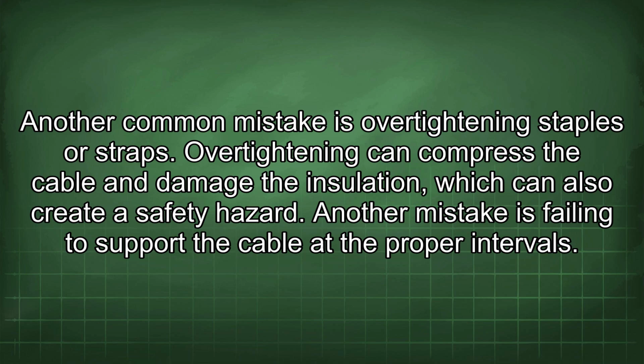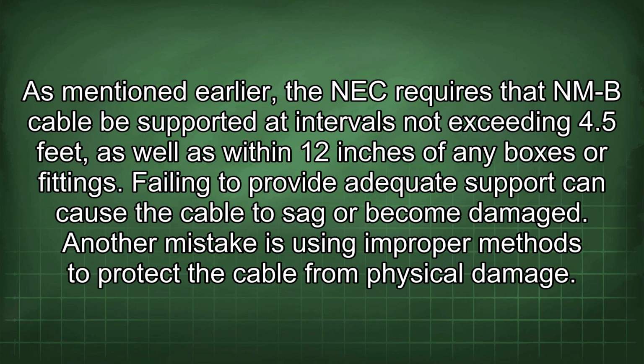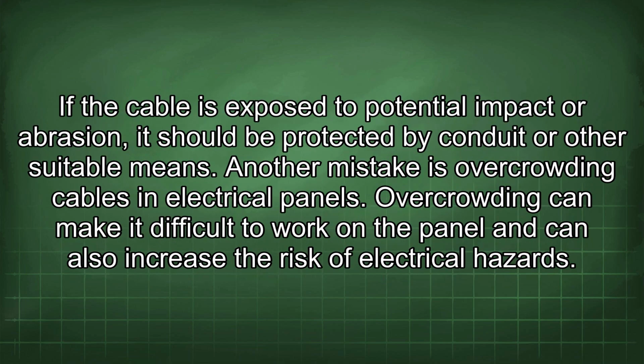Another mistake is failing to support the cable at the proper intervals. As mentioned earlier, the NEC requires that NMB cable be supported at intervals not exceeding 4.5 feet, as well as within 12 inches of any boxes or fittings. Failing to provide adequate support can cause the cable to sag or become damaged. Another mistake is using improper methods to protect the cable from physical damage. If the cable is exposed to potential impact or abrasion, it should be protected by conduit or other suitable means. Another mistake is overcrowding cables in electrical panels.